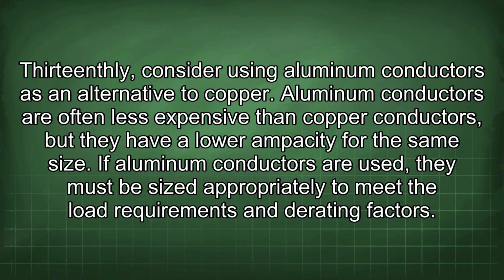13thly, consider using aluminum conductors as an alternative to copper. Aluminum conductors are often less expensive than copper conductors, but they have a lower ampacity for the same size. If aluminum conductors are used, they must be sized appropriately to meet the load requirements and derating factors.